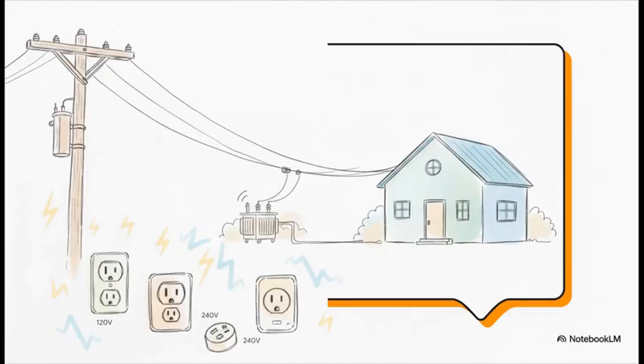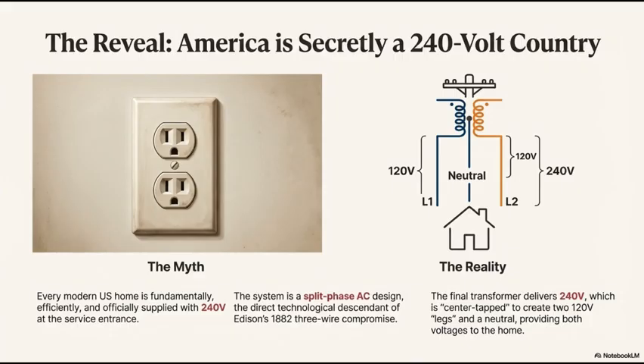Okay, so I think we have to ground this discussion in the engineering reality of the modern U.S. home. The U.S. electrical delivery is, in practice, a 240-volt system at the service entrance. We're not running our homes off single 120-volt wires. We leverage the split-phase mechanism, where you have two hot lines, L1 and L2, that provide 240 volts phase-to-phase for all the heavy loads: stoves, water heaters, central AC, EV chargers. This gives you a massive 48 kilowatt capacity on a typical 200 amp service.